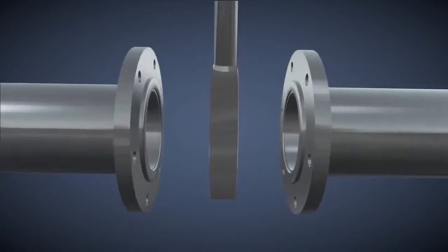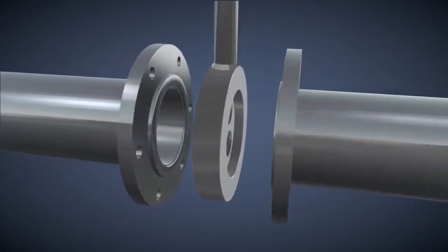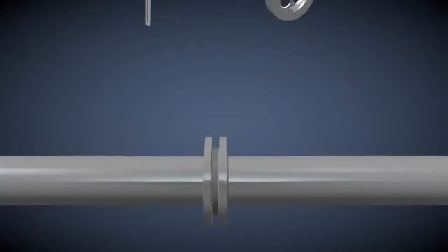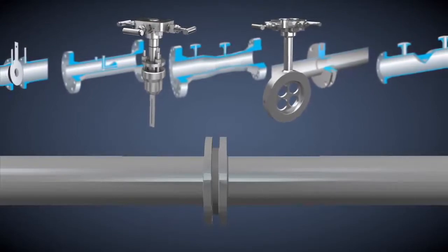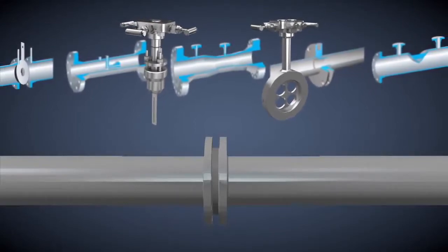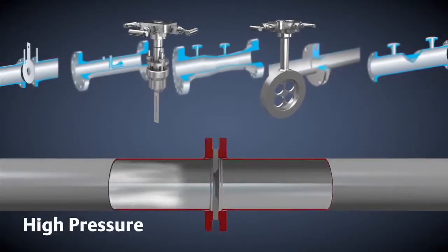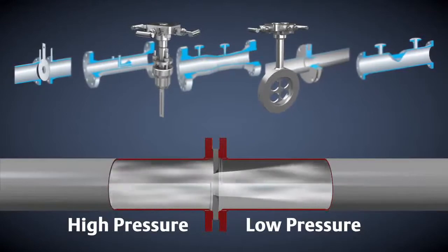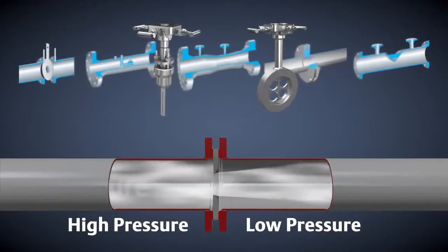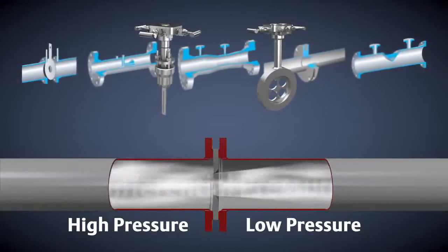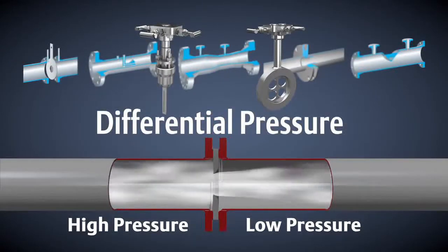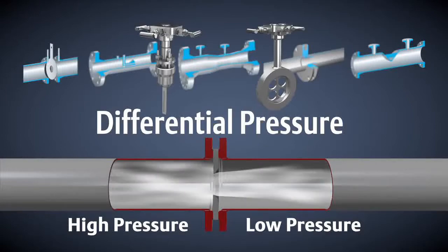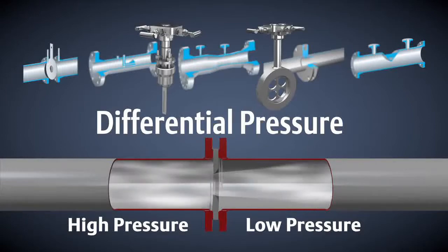Primary element selection is dependent on process conditions. All of these different primary elements have one thing in common: they constrict the flow in a pipe, causing a pressure drop from one side to the other. The difference in pressures is the differential pressure. The square root of DP is proportional to the flow rate.